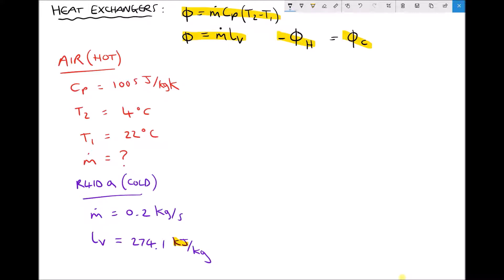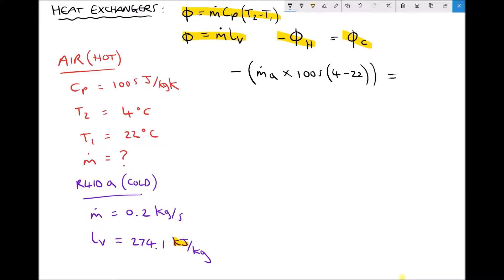For the hot fluid (air), we use the formula: minus dot-m × Cp × ΔT. The unknown is the mass flow rate of air. We know Cp is 1005, T2 is 4°C and T1 is 22°C. On the right hand side, for the cold fluid, we use mass flow rate of refrigerant times latent heat of vaporization: 0.2 × 274,100. We must remember to multiply the kilojoules value by 1000 to get joules — the correct SI units.